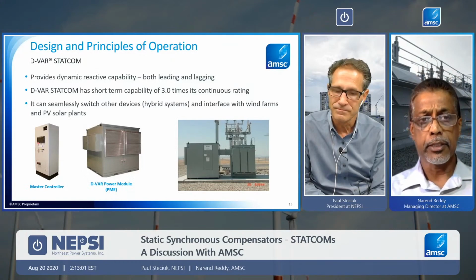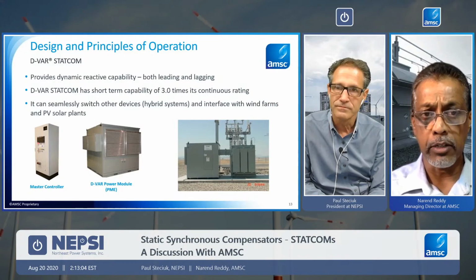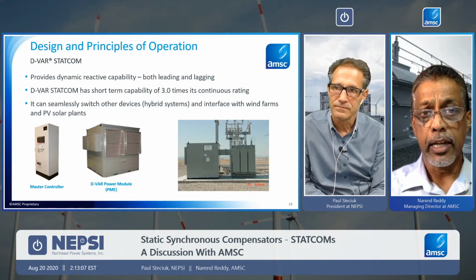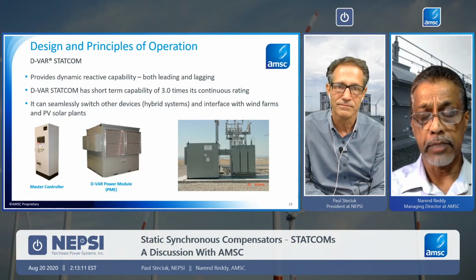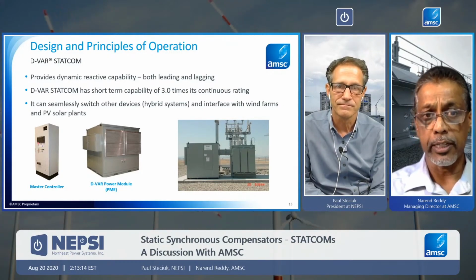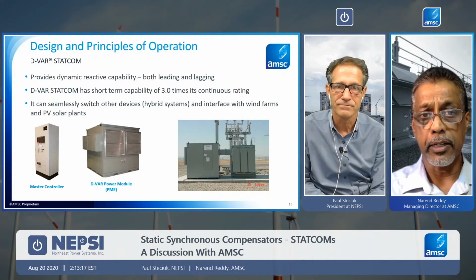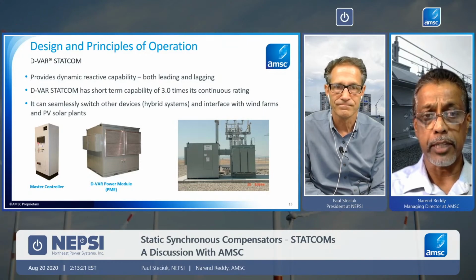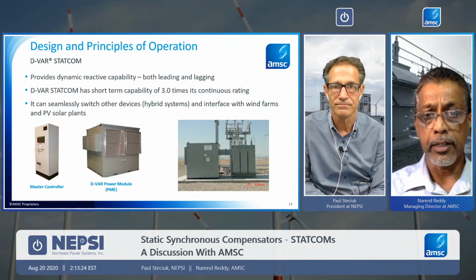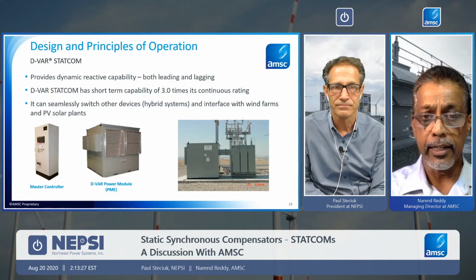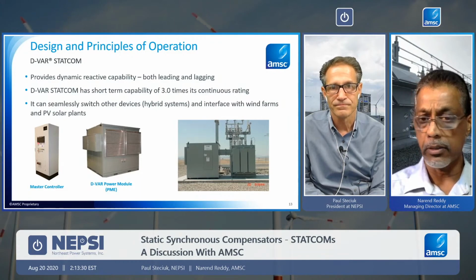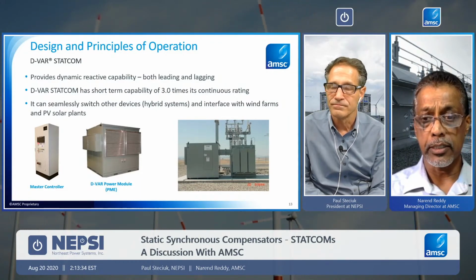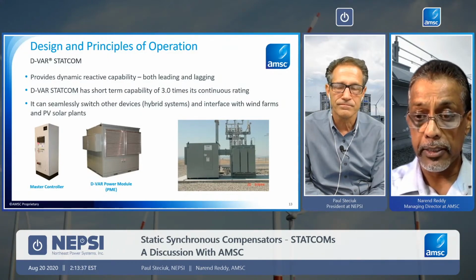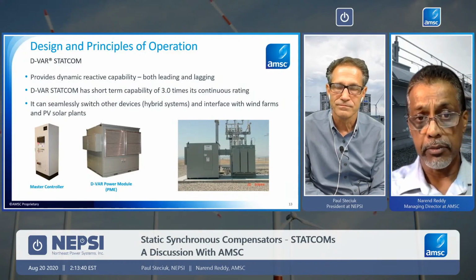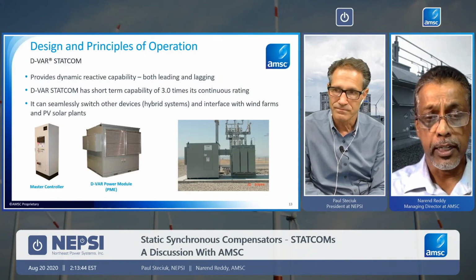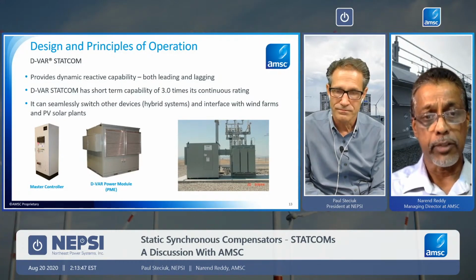So that's at a very base level. Taking that into how this is converted to a product for AMSC, our STATCOM is recognized by the name D-VAR STATCOM, which stands for Dynamic Volt Amp Reactive STATCOM Units. It is a proprietary trade name for the AMSC STATCOM. STATCOMs provide reactive capability both leading and lagging. So in other words, a 4 megavar or 10 megavar STATCOM unit is designed to be able to provide up to 10 megavars capacitive or 10 megavars inductive, depending on what the requirement is. But that's the nature of the inverter. It is essentially a control functionality that provides that.